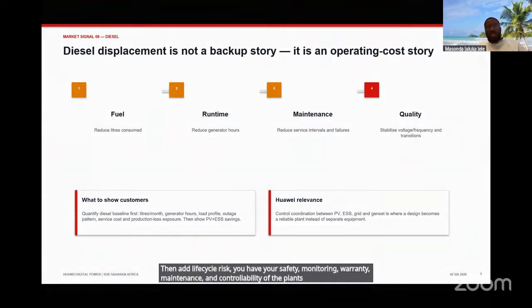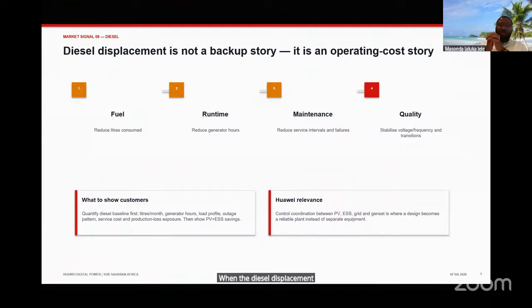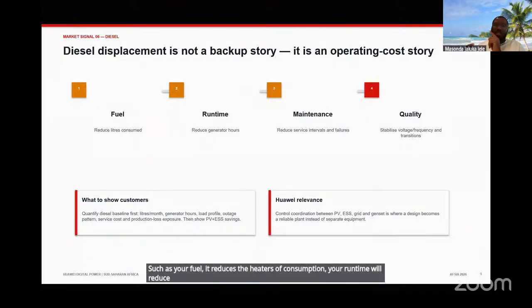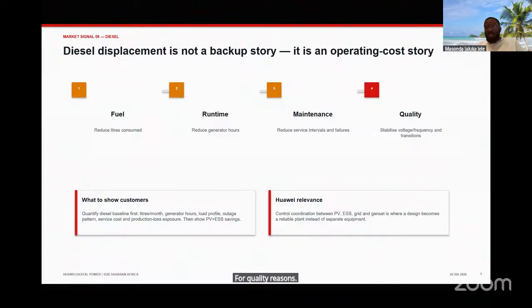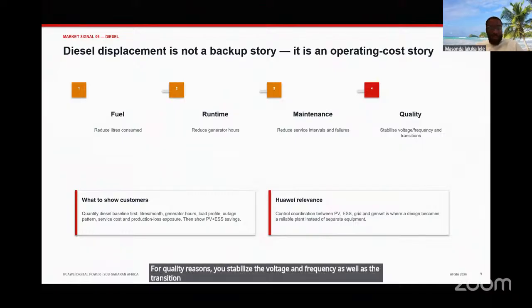On the diesel displacement side, it is not necessarily a backup story; it is an operating cost for our partners, such as fuel. It reduces the liters of consumption. Your runtime will reduce the generation hours. From a maintenance perspective, you reduce the service intervals and also the failures. For quality reasons, you stabilize the voltage and frequency as well as the transition of the grid.